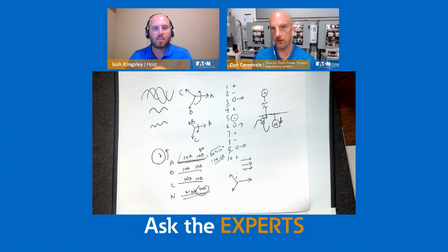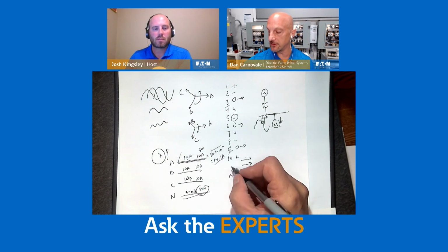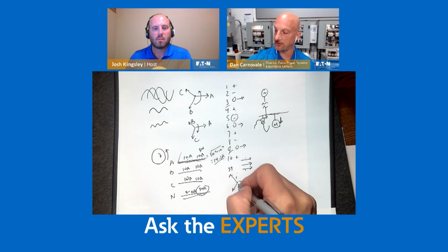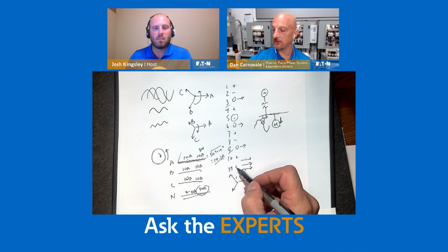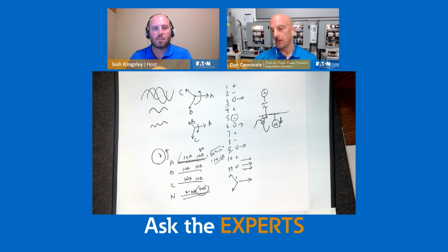And we talked about it earlier with the question about medium voltage and 480 volt systems, where maybe high frequency ones, you mentioned the 39th harmonic. If you keep expanding this list out, when you get to the 39th, it's going to be zero sequence. Positive sequence harmonics just add extra current to the system. It's like adding extra load on your wires, and it can overheat things. Negative sequence tends to make things want to go backwards. Zero sequence tends to add up again in a way.